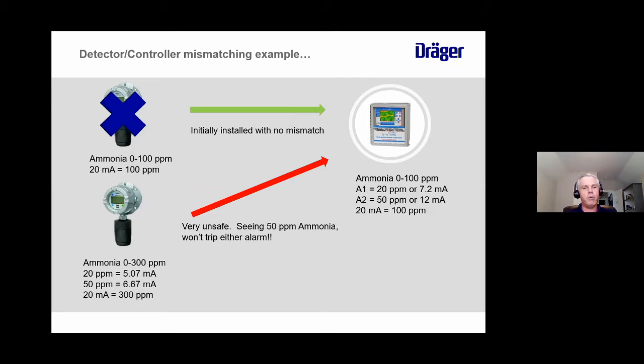So how does that apply to the Regard 7000? What the Regard 7000 is constantly doing is scanning that transmission from the transmitter to controller to make sure there's no mismatches. That's one of the ways we've increased the reliability of our operation. So we overcome that potential mistake that I've seen plenty of times in the past. And if you guys have been selling gas detection in the past, you've seen it probably too.